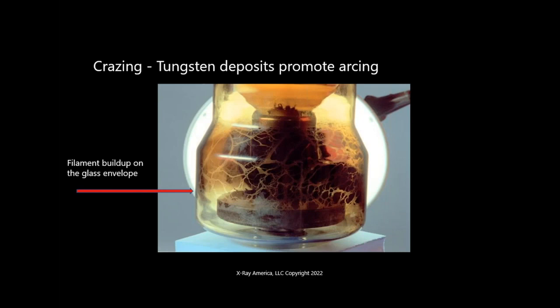Right, so what can happen is that over time, you can get crazing on the insert. This is tungsten that's built up around the core from the target, from the filament. What happens is this creates a path of arcing in the tube. So this will kill your tube. These are obviously end of life.